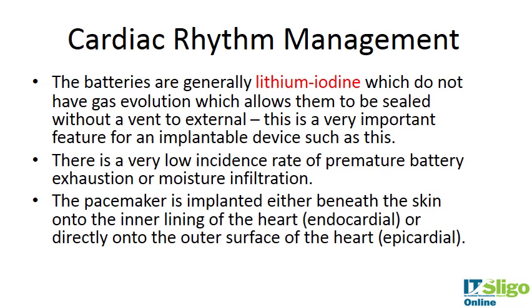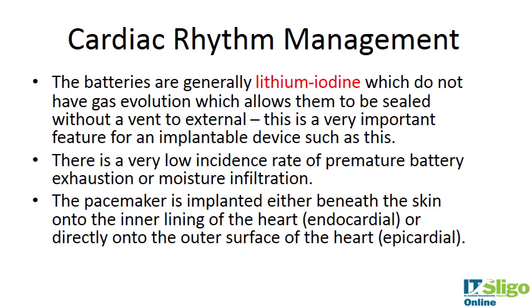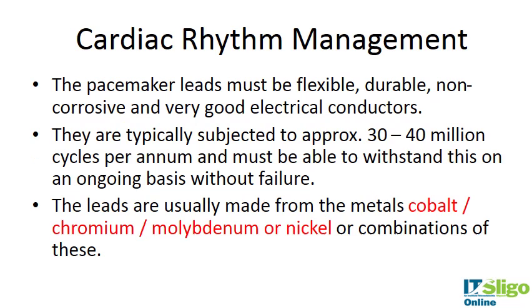The pacemaker is implanted either beneath the skin onto the inner lining of the heart — endocardial — or directly onto the outer surface of the heart — epicardial. The pacemaker leads must be flexible, durable, non-corrosive, and very good electrical conductors. They are typically subjected to 30 to 40 million cycles per annum and must withstand this cycling without failure.